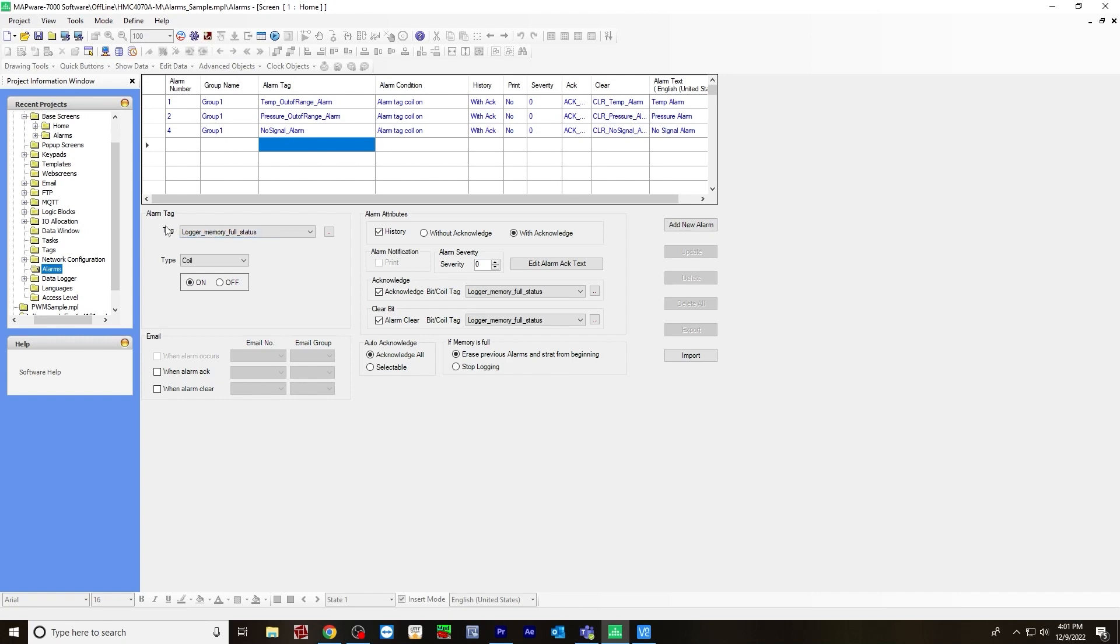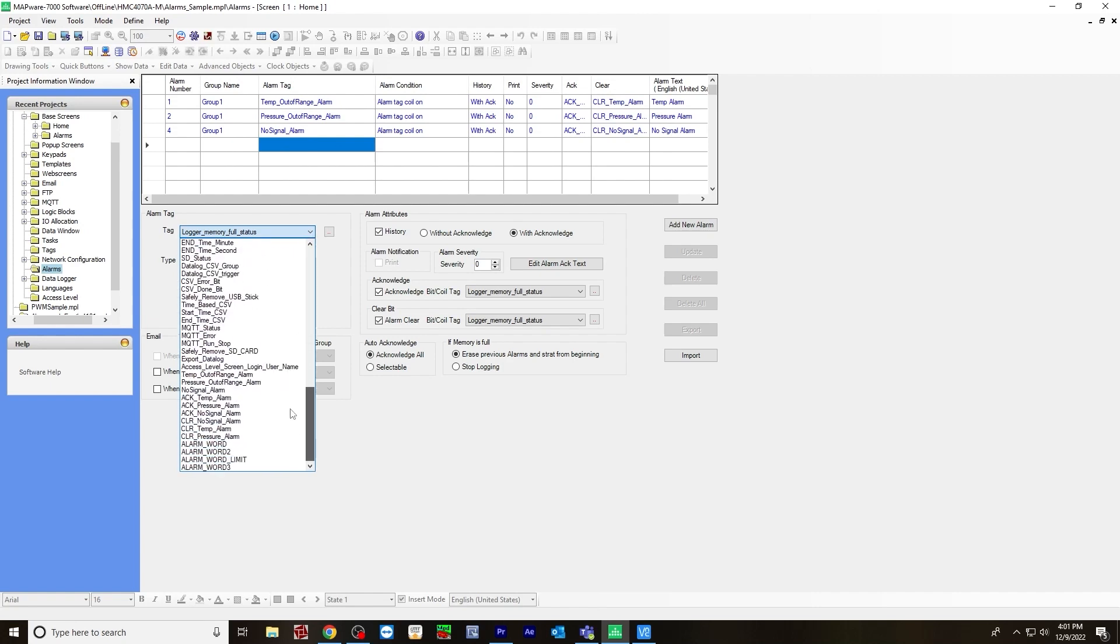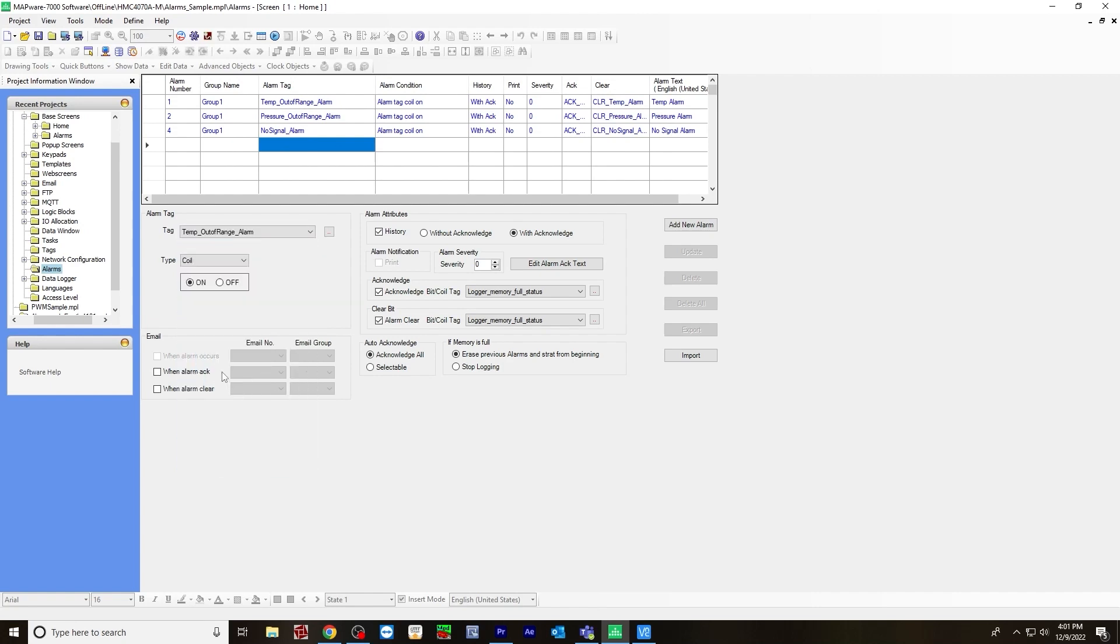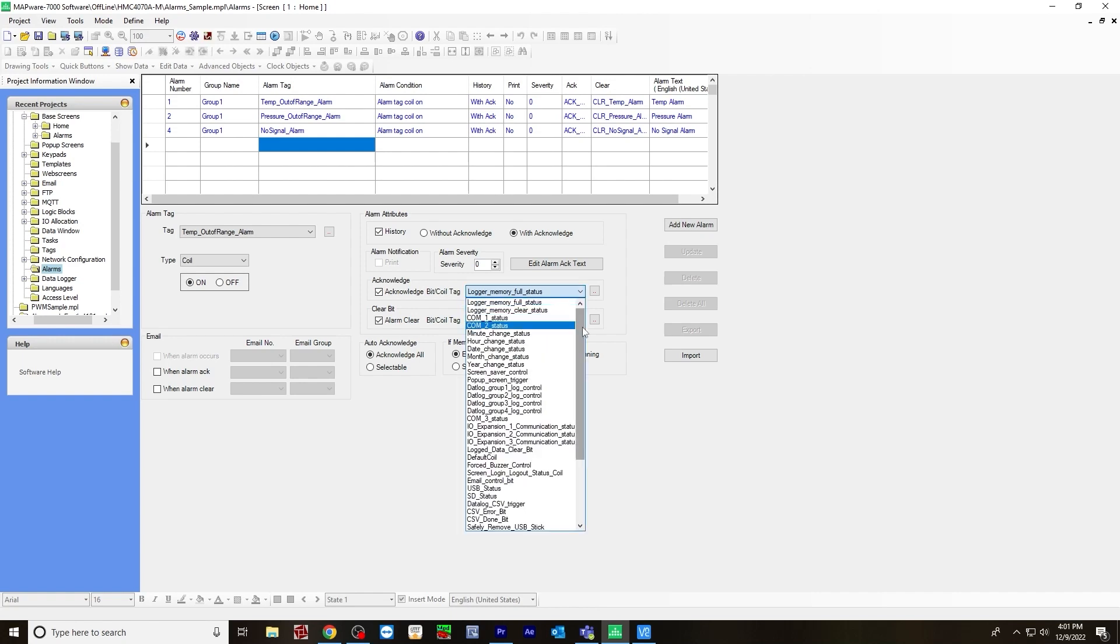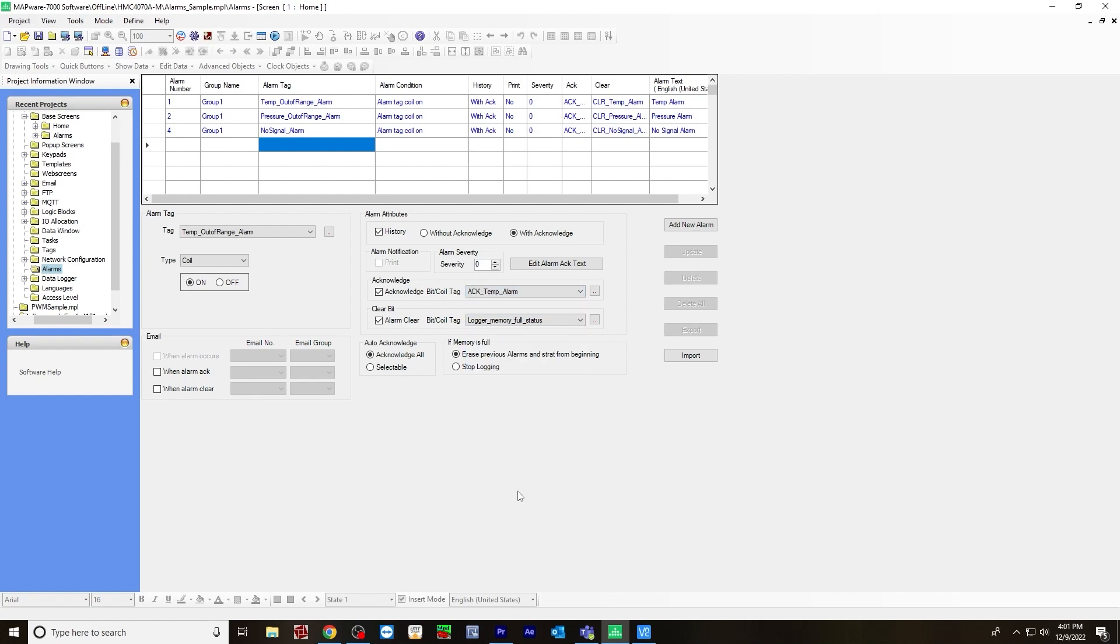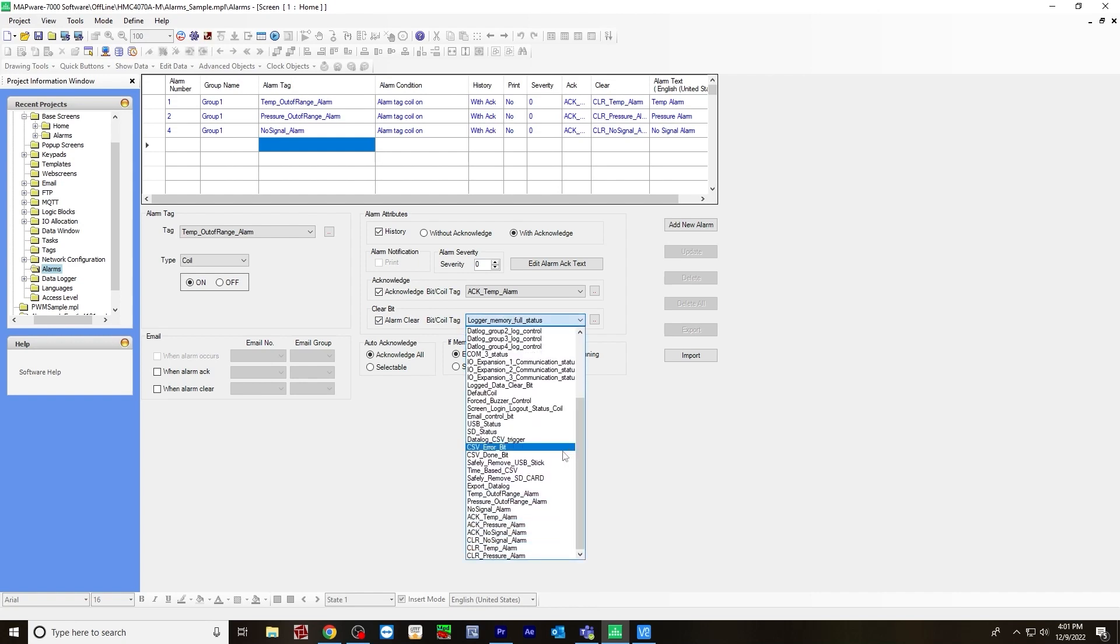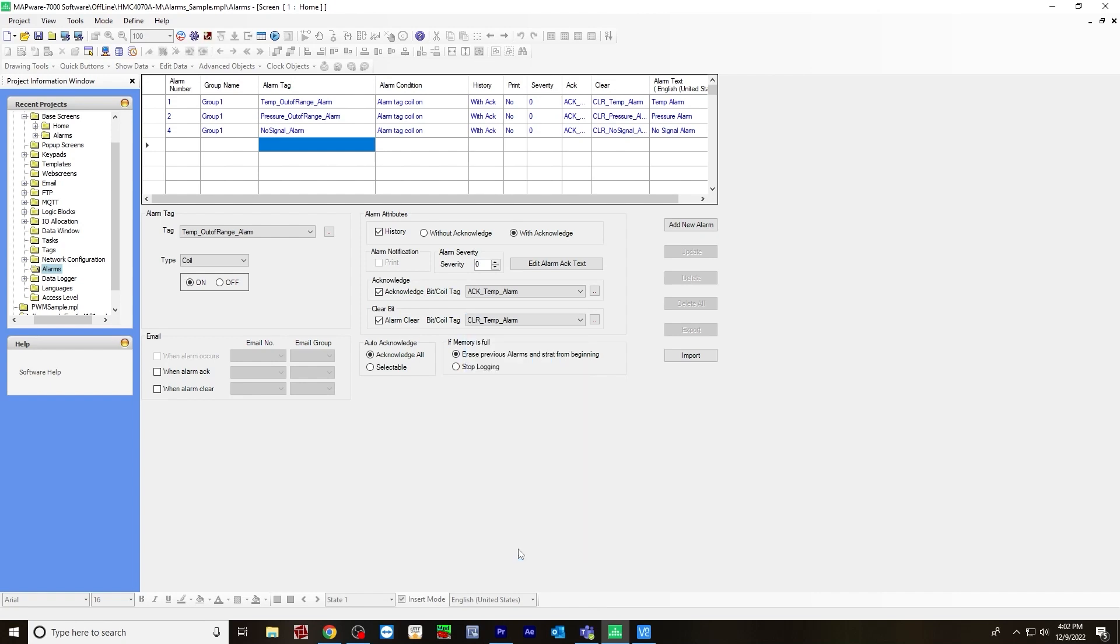Under alarm tag, I'm going to choose the temperature out of range. Type will be a coil. For alarm attributes, check off history with acknowledge. For the acknowledge tag, you'll choose the acknowledge temperature alarm that you created earlier. And for a clear tag, choose the clear temperature alarm.